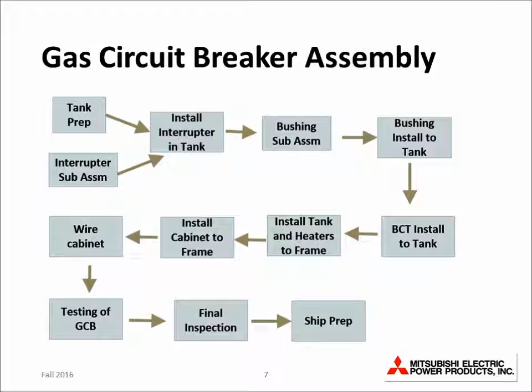Bushing current transformers, or BCTs, are installed onto the tanks. At this point, the tanks are installed on the main breaker frame, again using the crane. If heaters have been requested by the customer, then they are also installed at this step. Initial wiring and preparation is conducted by the technician on the breaker cabinet, and the cabinet is then installed onto the breaker frame using the overhead crane. The frame is then moved to the main work cell for final wiring of the electrical connections and begins a lengthy testing process to guarantee product functionality. The breaker then undergoes final inspection by Mitsubishi quality personnel.